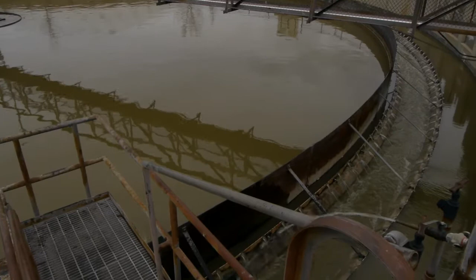The flow of sewage is beyond the control of the plant, and therefore they need to know how much to expect. What's the average flow per day? What's the peak flow? How much more is the maximum flow compared to the average flow during a year? A great way to deal with the question is to ask, what's the percentage increase at the peak over the average? We get the percentage by dividing the peak daily flow by the average flow and then multiplying by 100. So for January, 12.4 over 11.3 multiplied by 100 equals 110.